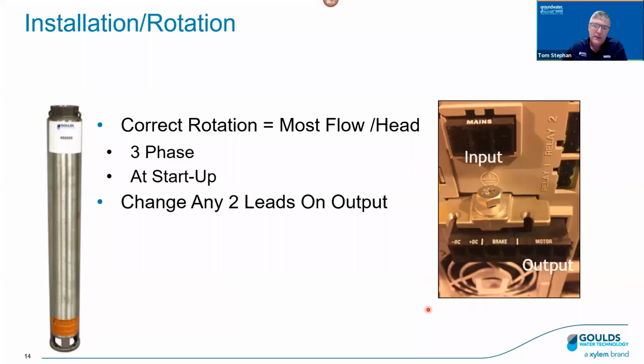Now with a submersible, it's not quite as easy, right? It's because we probably are not going to pull the pump in to check the rotation right at the coupling, right? So, but for a submersible, we know that the most flow and head are the correct rotation. So you might have to do a comparison with the two different directions, right? So we are talking about three-phase here, and normally at startup, right? And so we always want to check the rotation at startup. And again, we're going to change any two leads on the output if we have a drive.